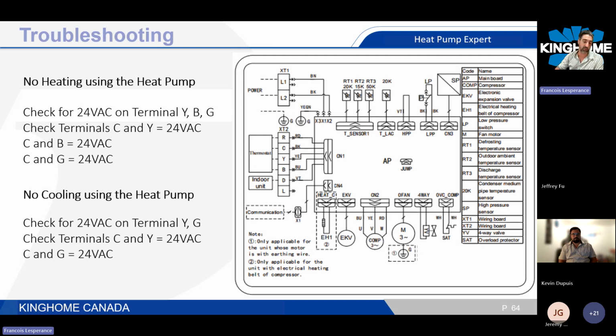So you just have to make sure you make a clear difference between an internal issue from the wiring or thermostat or furnace, or an external issue like with the outdoor unit. Same stuff if you don't have cooling, where now for cooling, we don't use the B terminal, so it will be C and Y, and from the thermostat it will be powered at the G as well.